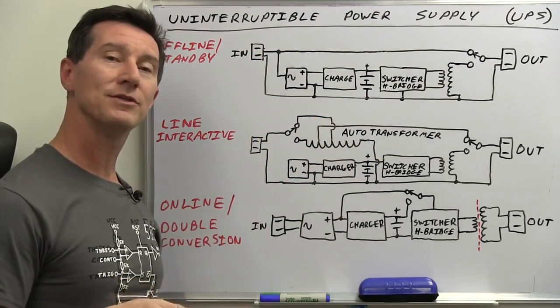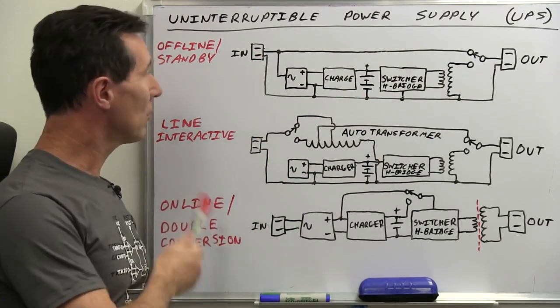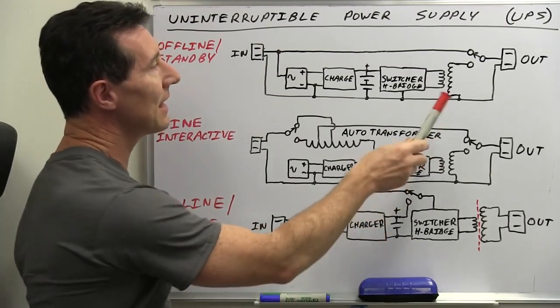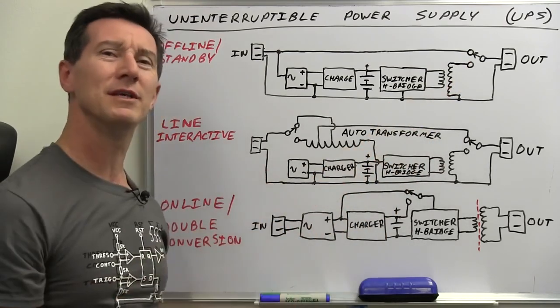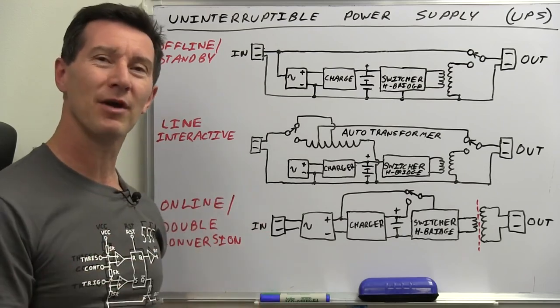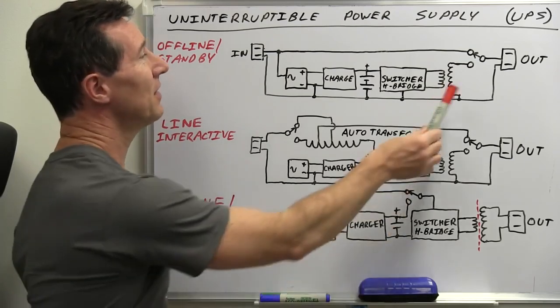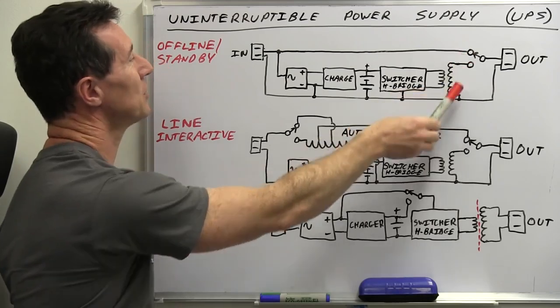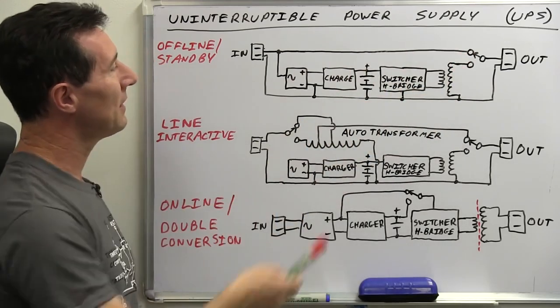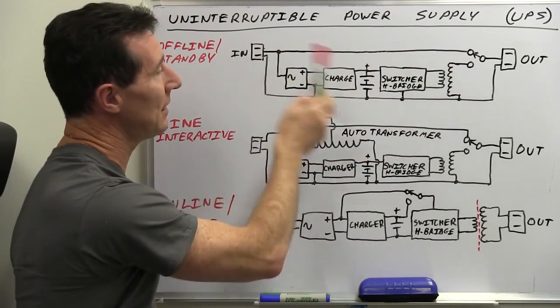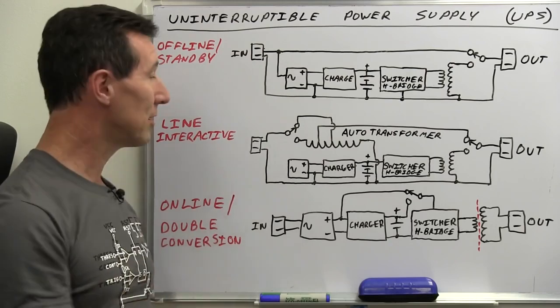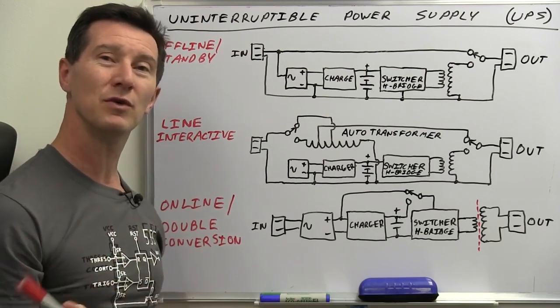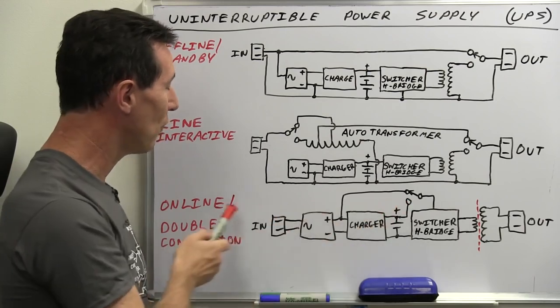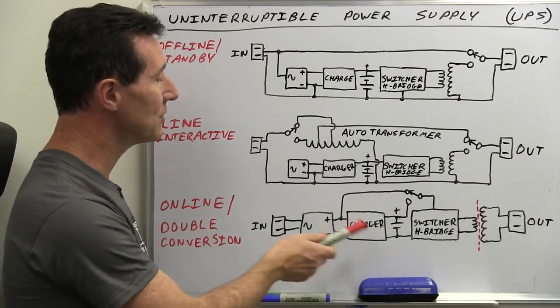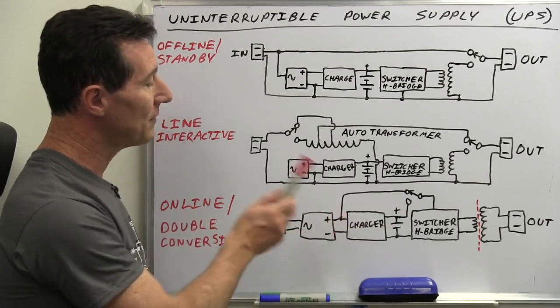And the other main reason why you want to use the online one compared to the offline is that if you've got a really noisy mains and it's always dropping, there's always brownouts and dropouts and all sorts of stuff, you don't want this thing to be continually switching back and forth between the input and the battery, for example. You're much better off in those noisy and troublesome environments to go for an online conversion where it's just always running from the DC here.